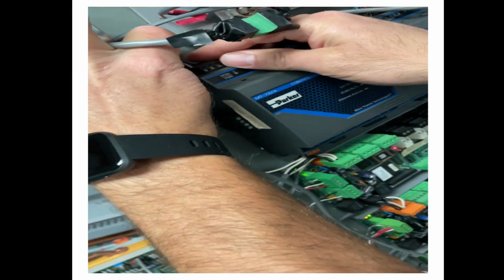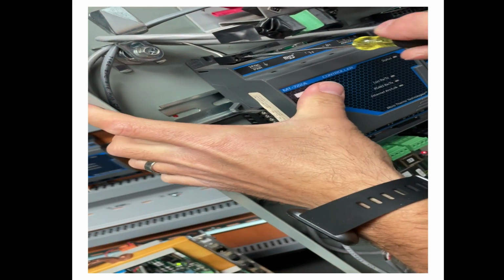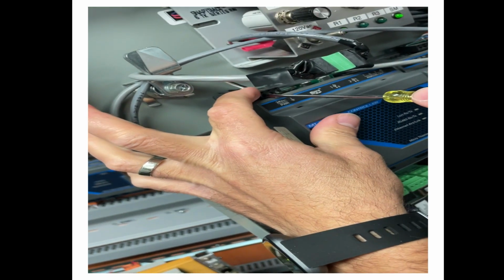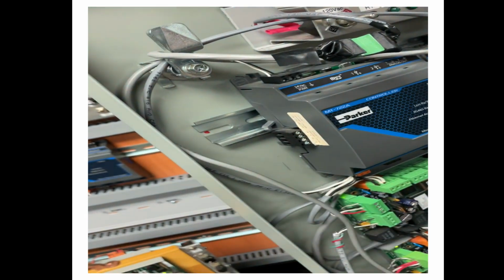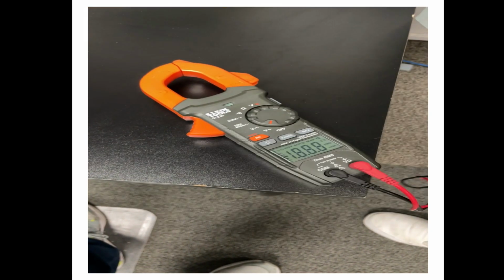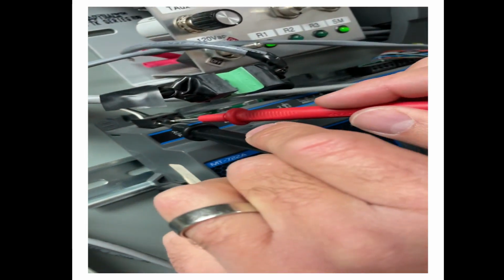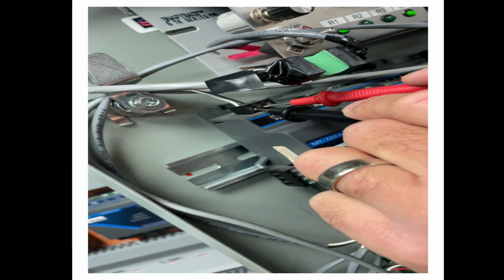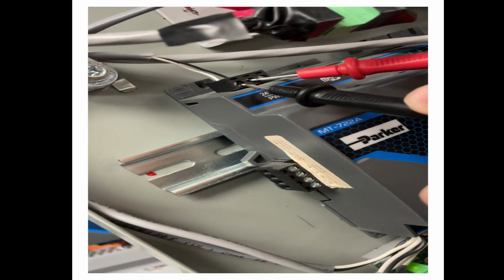Next, check the power wiring coming to the power connector at the top. Make sure the wires are tight and there are no strands or frays. Again, check the lugs, make sure they are properly tightened. And then finally, with a good quality multimeter, check the voltage coming to the node. It should be 24 volts nominal, plus or minus 10 to 15%.